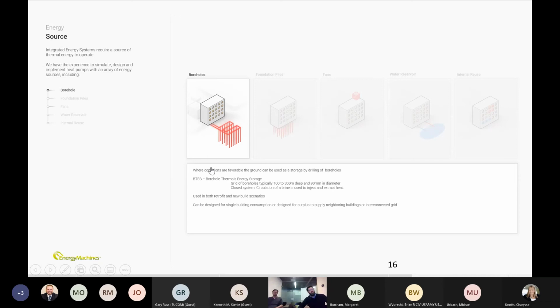The one we've had the most experience with, primarily in situations where there's bedrock, but also limestone, is BTES: borehole thermal energy storage. I don't think this is foreign to USACE. I believe it's actually one of the largest systems in the world. Basically, BTES is a grid of boreholes roughly 100 to 300 meters deep, depending on ground conditions, and 90 millimeters in diameter.